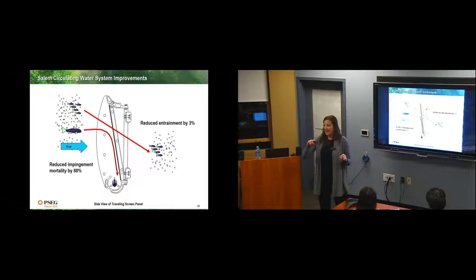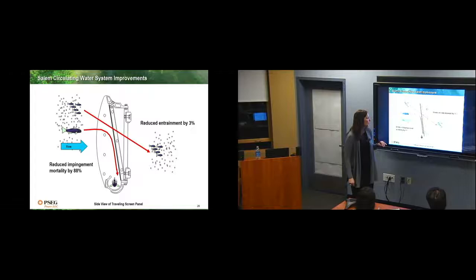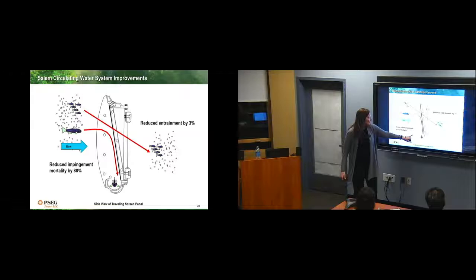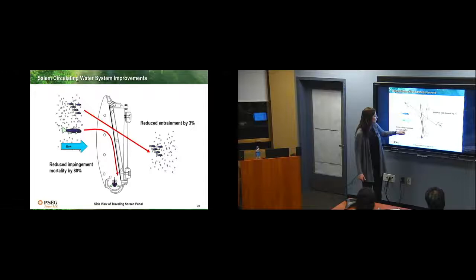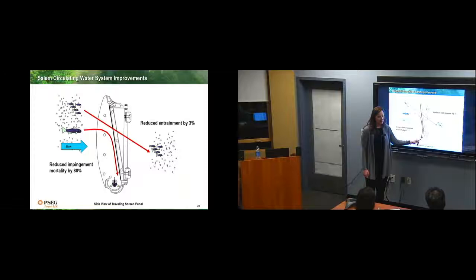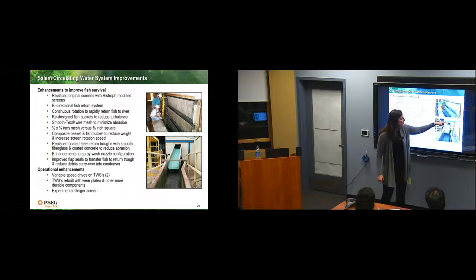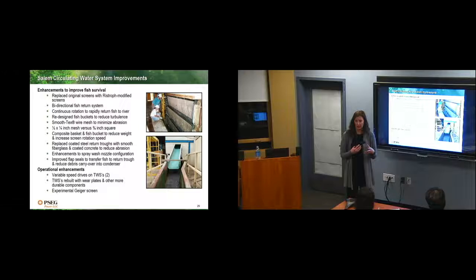Baby fish and fish larvae can get through the screens, and that's what would go through the system. It doesn't mean that they're automatically being killed because the water temperature is just getting heated up a little bit. We're not allowed to go past 17 degrees. If we went to 17.1, we would be shut down until we fixed it. So our temperature is maintained constantly. But this is what you hear with fish that are being taken out of the environment because of our nuclear plant. There's also a little trough at the bottom of each of these screens. So as a fish comes, it's no longer getting impinged. It gets put into this little trough. The cutest fish ever, right? This little fish gets in the trough. And then what happens is, as it goes around, there's a low pressure rinse to wash the fish off. And then they get the slide down our little nuclear Disney World. They go right back into the river.